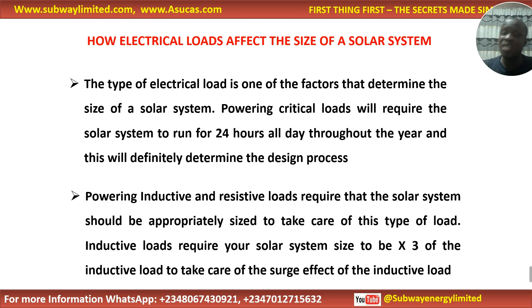Powering inductive and resistive loads requires that the solar system be appropriately sized to take care of this type of load. Inductive loads require your solar system to be sized three times the inductive load to take care of the surge effect of the inductive load. But I told you that most times you don't take all these things into consideration, because imagine somebody is using... let's leave that. When we get to system design, we'll expatiate so that you understand it.